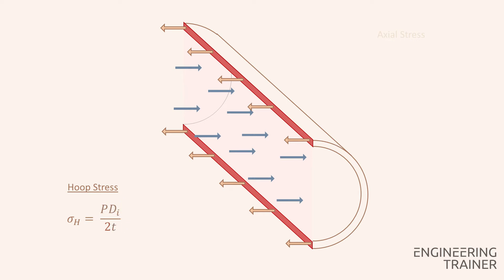Commonly the equation is expressed using the outer diameter instead of the inner diameter. This will always give a higher stress value since the outer diameter is by definition larger than the inner diameter. The resulting equation states that the hoop stress in a pressurized piece of piping is roughly equal to the inside pressure times the pipe outer diameter divided by 2 times the thickness.